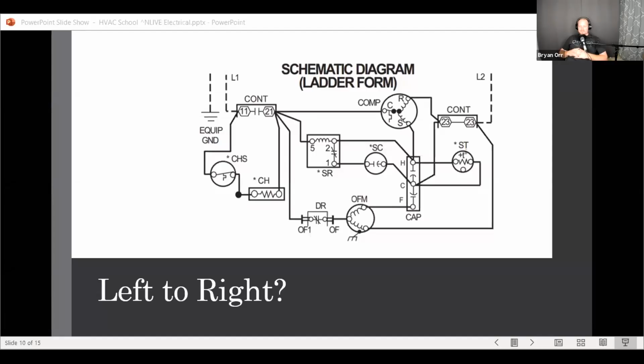This particular unit was designed for medical space, but then they converted it into a pharmacy, and it had a 2-speed, 3-phase motor with dual contactors. So low speed would energize one contactor, one would drop out, energize the high-speed contactor. Air balancer went out and was trying to do an air balance, and when he ran the unit in cooling, it started short cycling. I got sent out there to go look at the problem, and so I started going through all the voltages, checking everything.